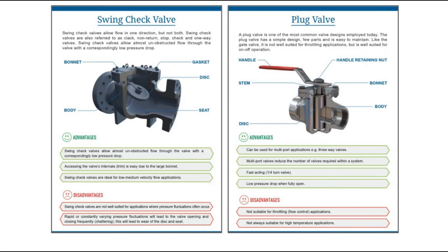Plug valves are one of the most common valve designs employed today. The plug valve has a simple design, few parts, and is easy to maintain. Like the gate valve, it is not well suited for throttling applications but is well suited for on-off operation. The parts include the handle, stem, disc, bonnet, body, and handle retaining nut. Advantages include use for multi-port applications such as three-way valves, which reduces the number of valves required in a system. It is a fast-acting quarter-turn valve with low pressure drop when fully open, but again not suitable for throttling or high temperature applications.